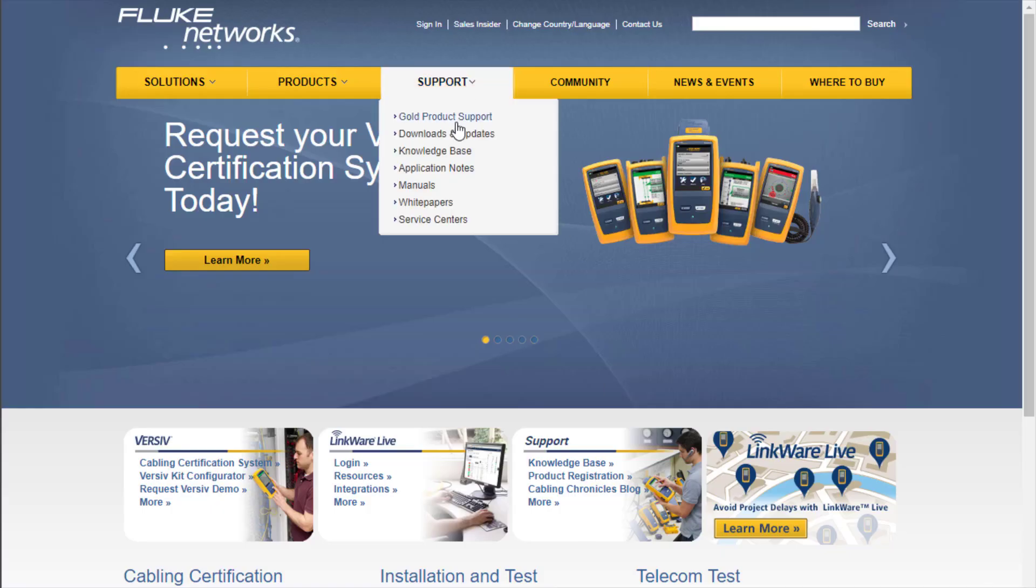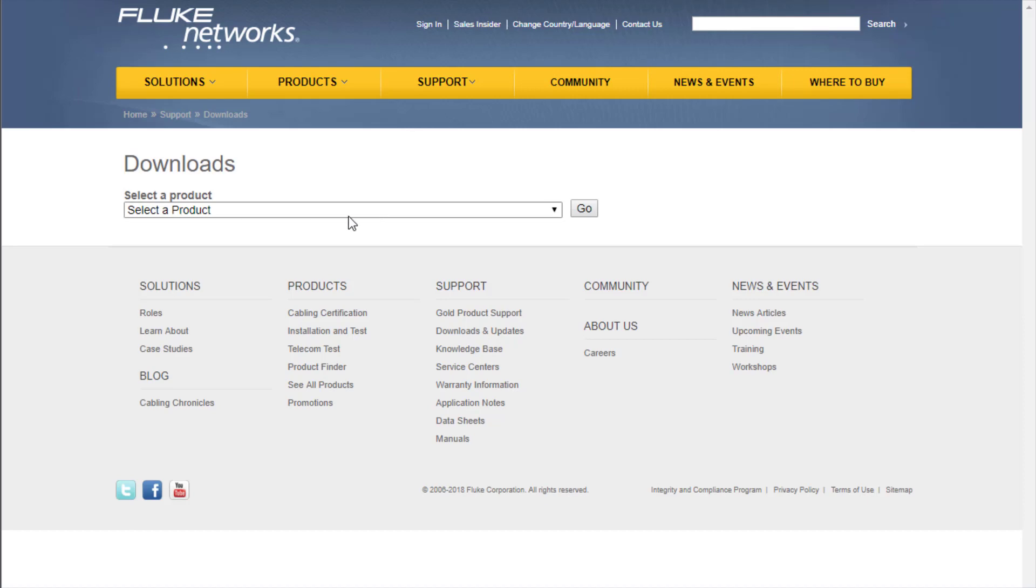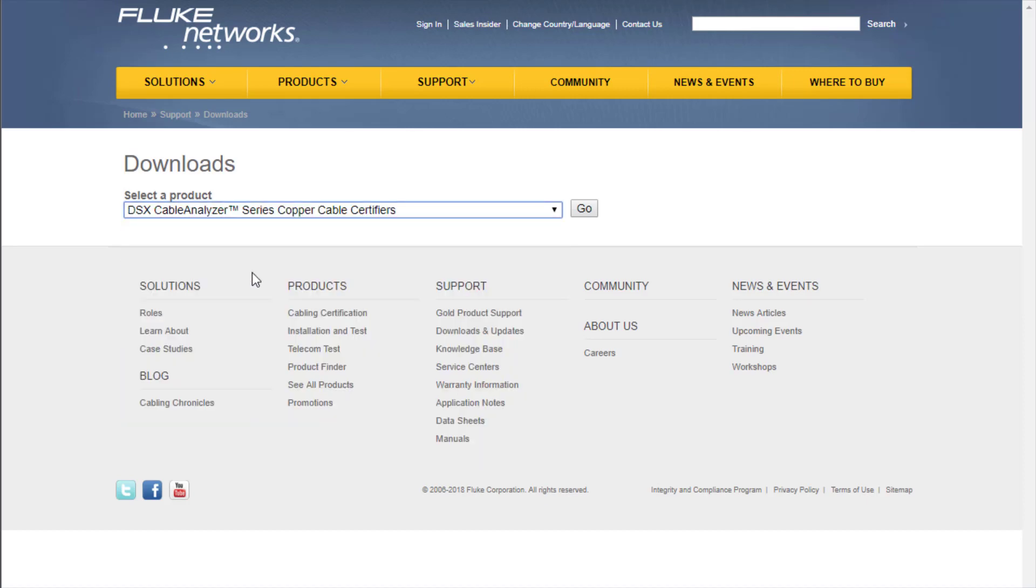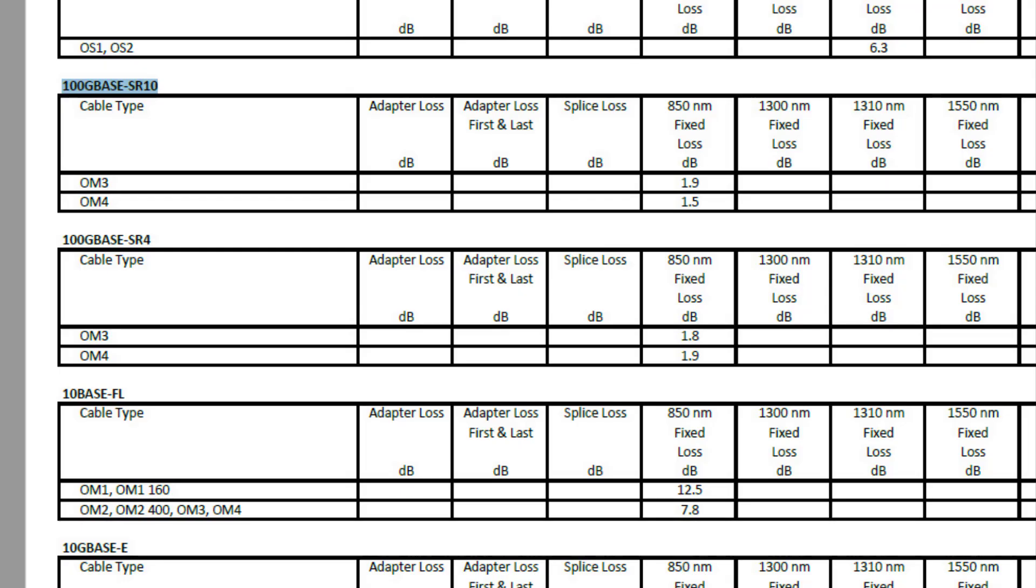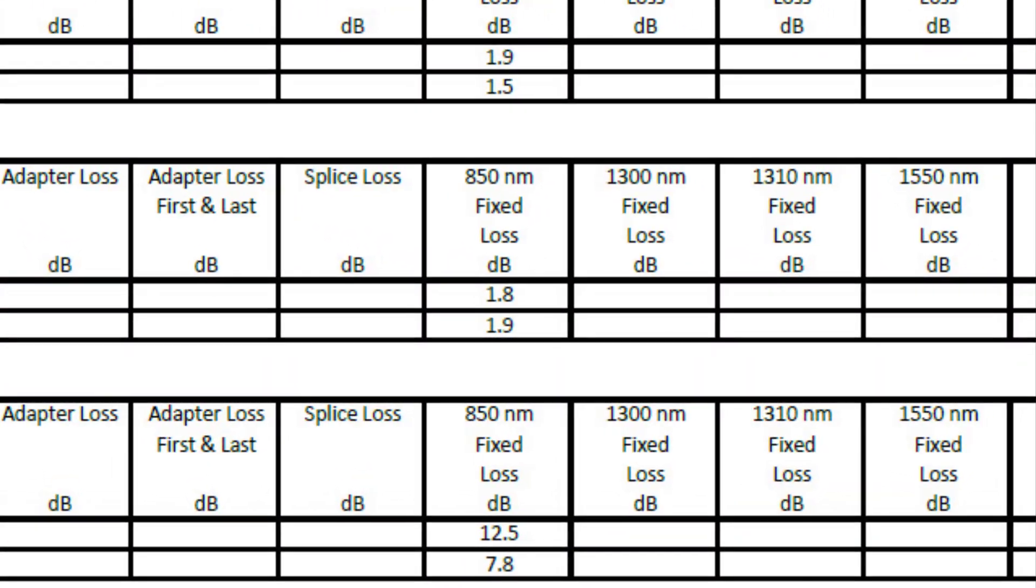We'll be testing this MPO trunk cable to ensure it will support a 100G base SR. We know the fiber we're using is OM4. Now we can go to the Fluke Network's website and find the limit lines. This document shows us the maximum allowable loss based on the application and the fiber type. In this case, we can see that the maximum loss for a 100G base SR over OM4 fiber is 1.9 dB. Before we run the tests, I will set the loss limit on the light meter.